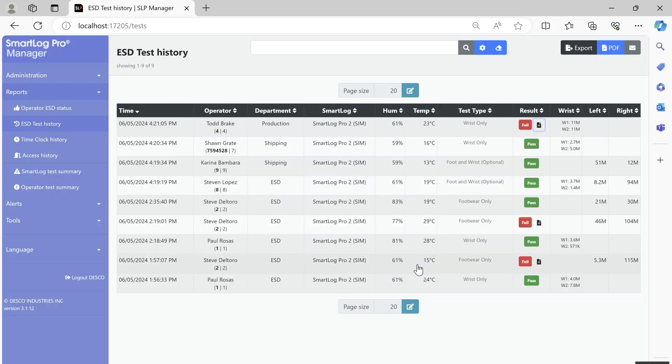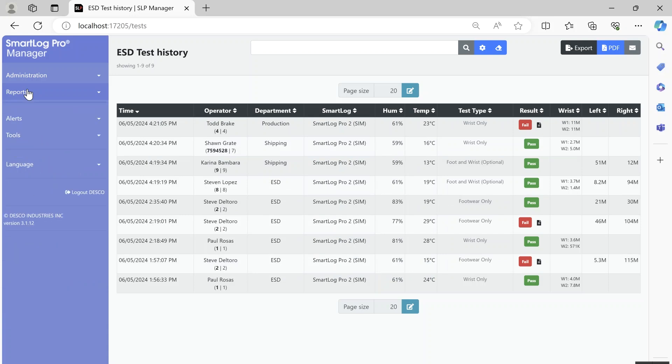SmartLog Pro Manager generates automated reports that may be emailed to track short-term and long-term corrective actions. Management of the SmartLog Pro 2 testers through the web app allows remote changes to display settings, test limits, and test parameters.